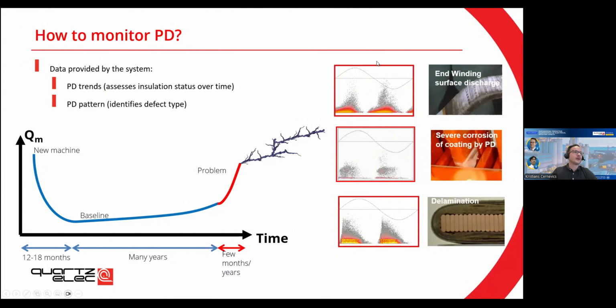Once from this graph you get your QM value, which is just a statistical value of the charge, a characteristic charge that is being discharged in your machine, we can plot it with time. Usually for new machines, this can be quite high up. It will go down and reach a trend, a baseline. And then for many, many years, the baseline is going to stay almost the same. So it means that the insulation is not really changing or deteriorating that fast.